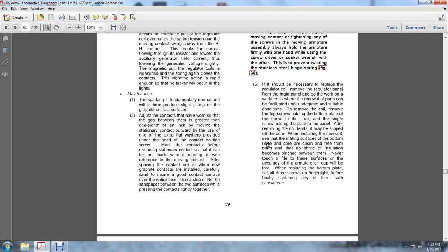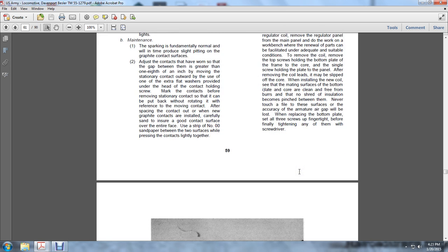See that the mating surfaces of the bottom plate and core are clean, free of burrs, and that no shredded insulation becomes pinched between them. Never touch a file to these surfaces or the accurate armature air gap will be lost. Replace the bottom plate with the three screws, finger tightening them before the final tightening of any of them with a screwdriver.